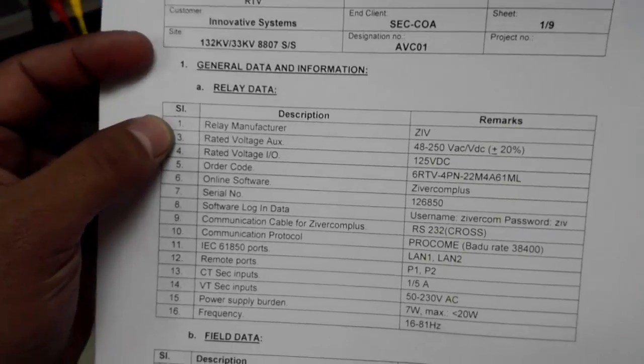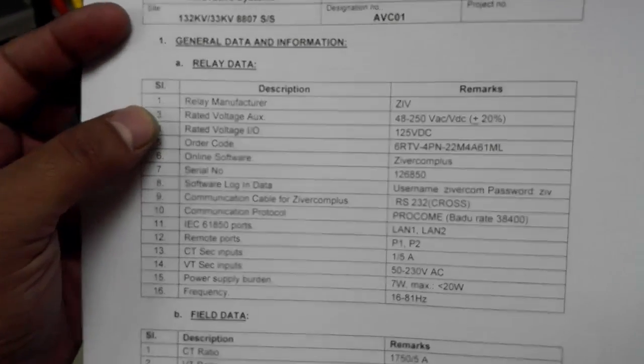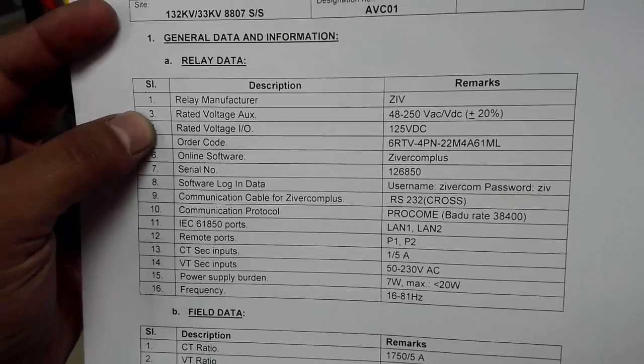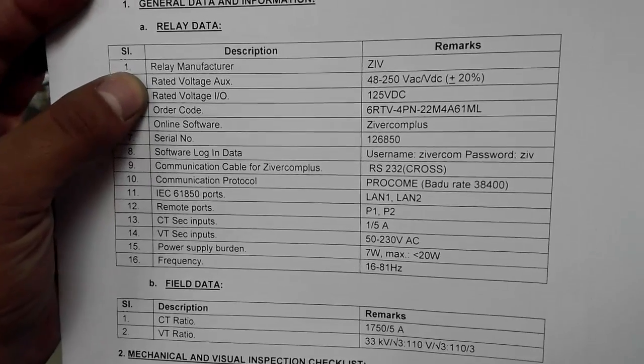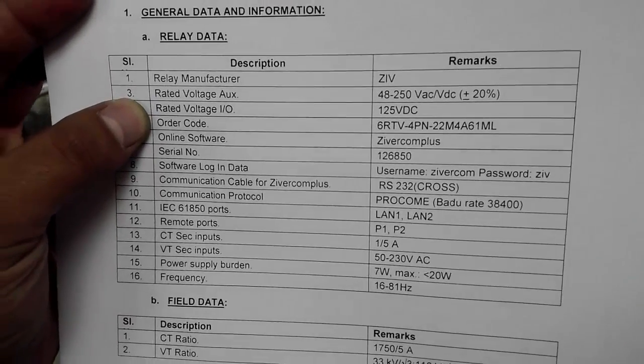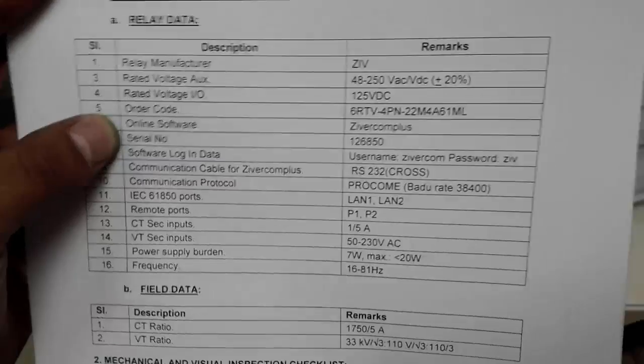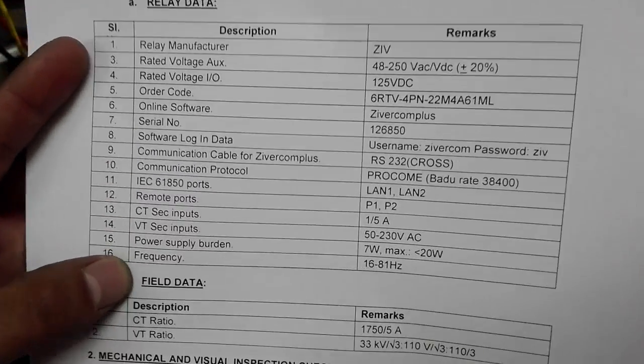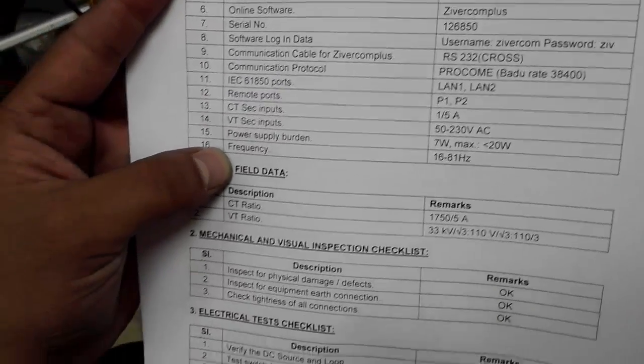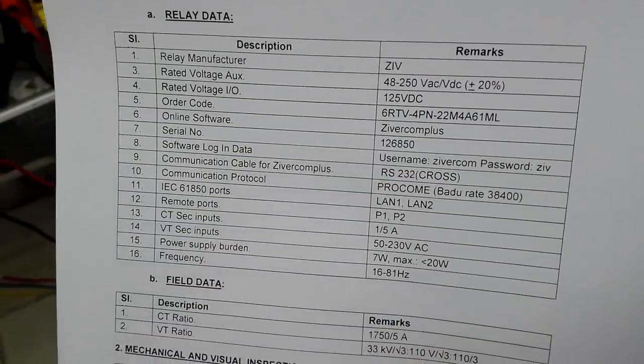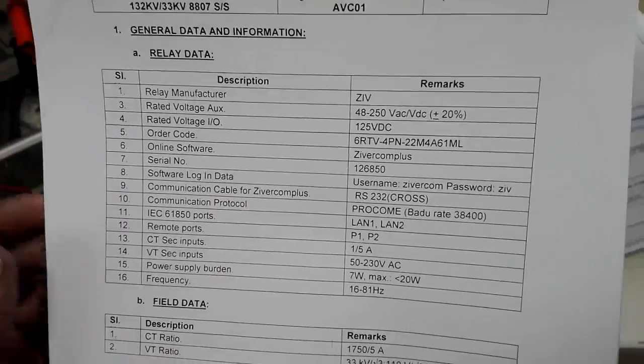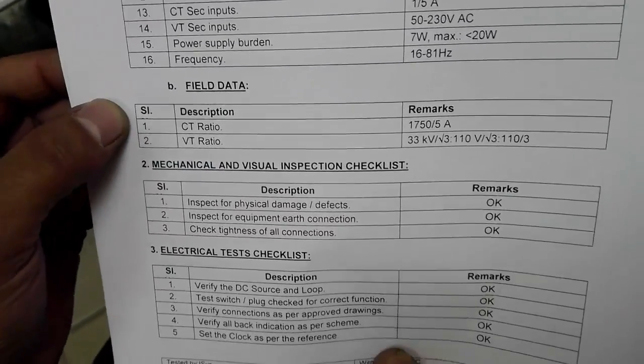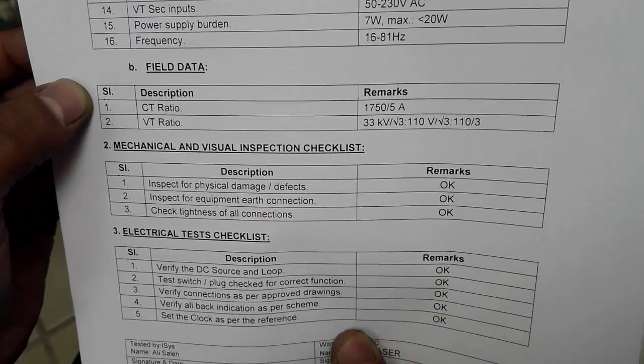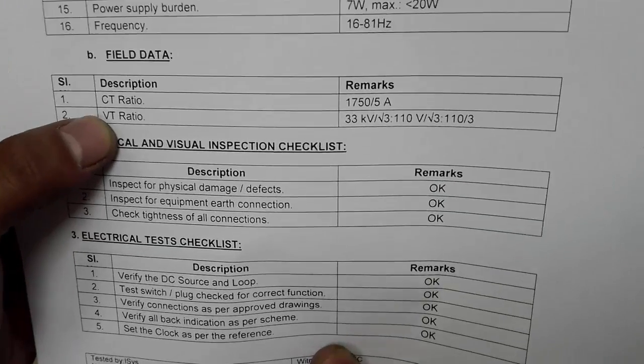relay data. It is the relay manufacturer name, that is ZIV. Some other ratings are given here: rated voltage, rated voltage input output, order code, and up to frequency. So all the information is labeled here. According to this range, we will follow these instructions. After this, this is field data, CT ratio and VT ratio.